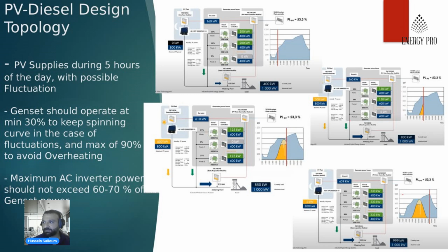On the other hand, we have to design the solar system not to exceed 60 to 70% of the maximum load capacity, because we have to keep that room for the generator to operate at 30%. So, taking this example, this is a 1 megawatt project, and we have designed it at 600 kilowatt solar cell or 800 kVA solar setup, and we have put three generators of 400 kilowatt.